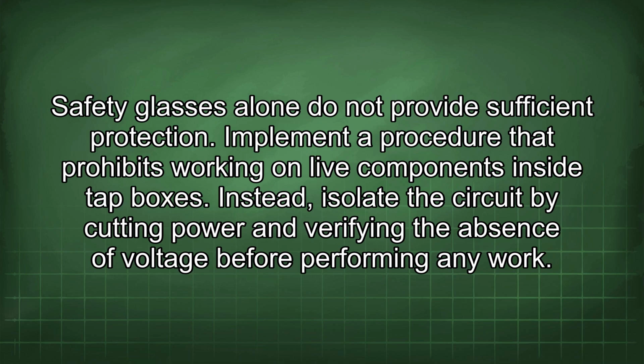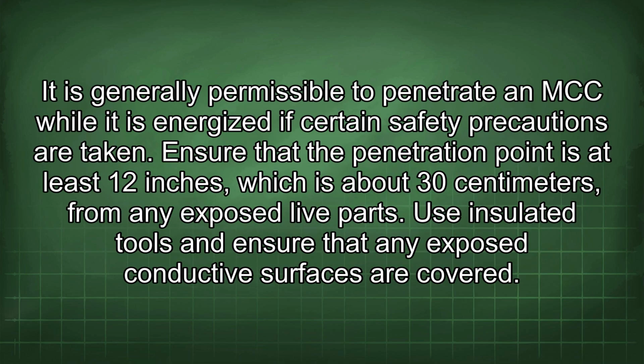Implement a procedure that prohibits working on live components inside tap boxes. Instead, isolate the circuit by cutting power and verifying the absence of voltage before performing any work. It is generally permissible to penetrate an MCC while it is energized if certain safety precautions are taken. Ensure that the penetration point is at least 12 inches, which is about 30 centimeters, from any exposed live parts. Use insulated tools and ensure that any exposed conductive surfaces are covered.